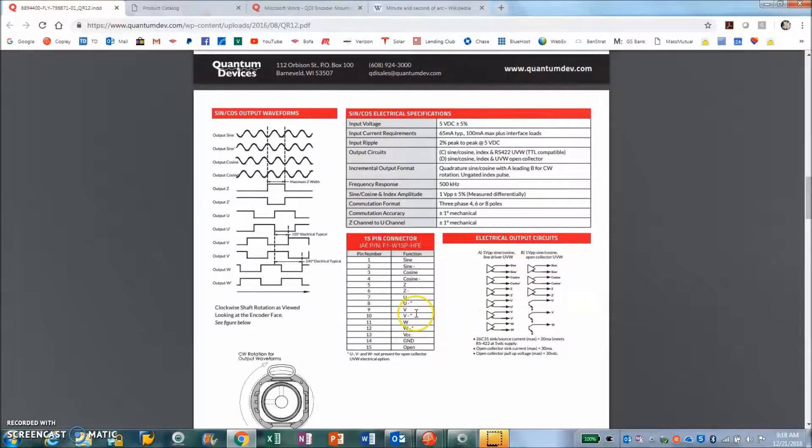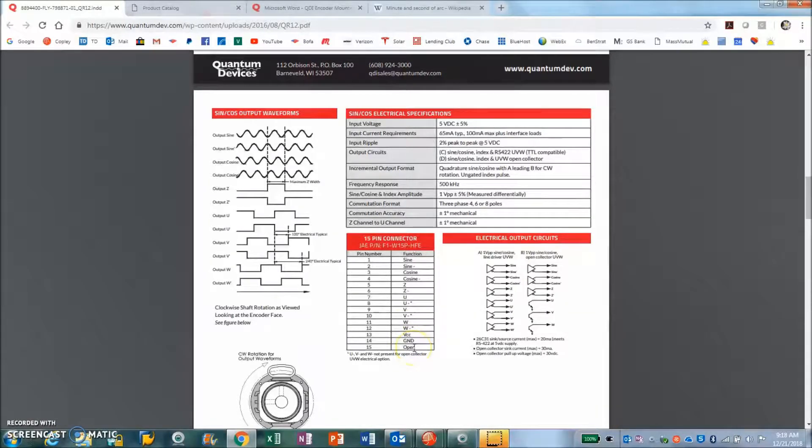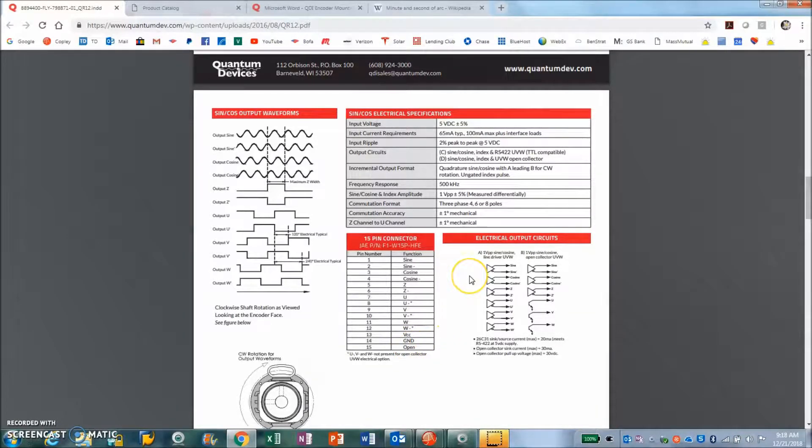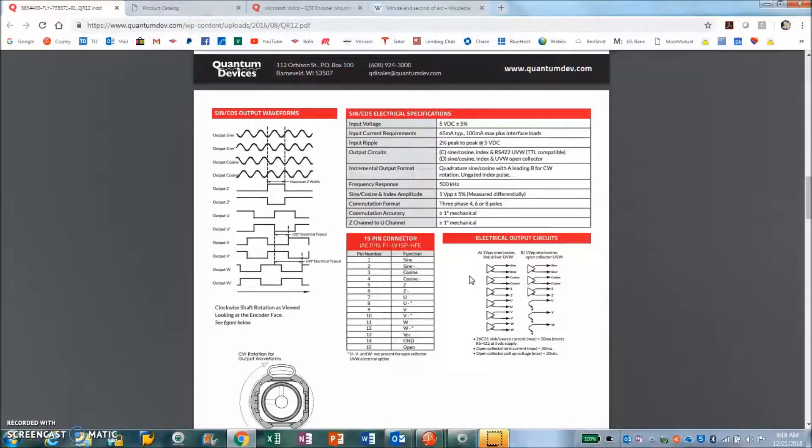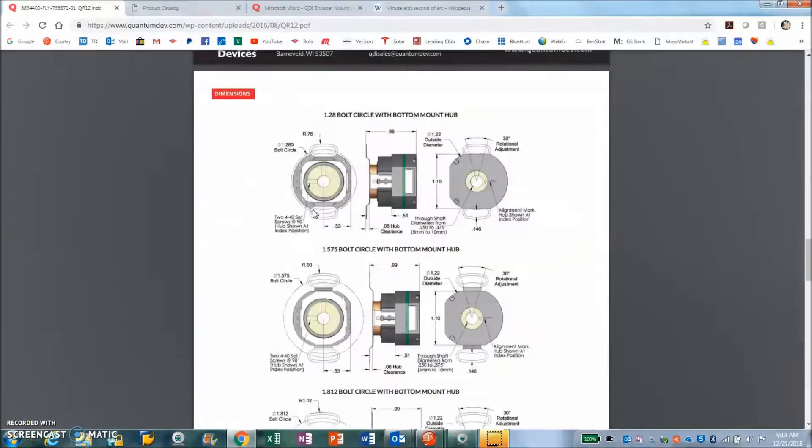Of course it's plus five and ground, and the cable should have a shield and the shield should be connected to earth. All shields must be connected to earth.